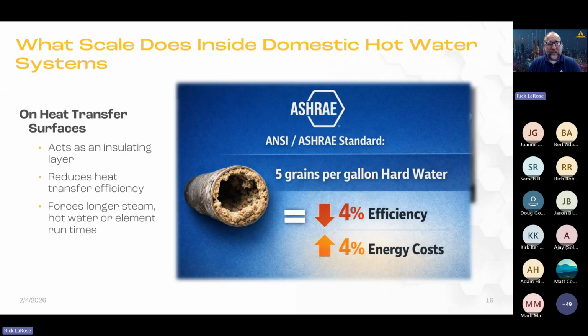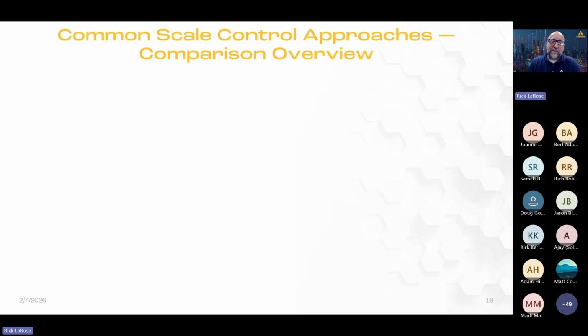So domestic water systems are not always a big energy hog from a consumer standpoint, but that's also lost capacity where your heaters can't keep up, maybe you're not providing enough hot water, or you're having to run multiple heaters simultaneously to maintain load, whereas you could just run one cleaner. By keeping these heaters clean and keeping scale off these surfaces, we can keep them running at peak efficiency.